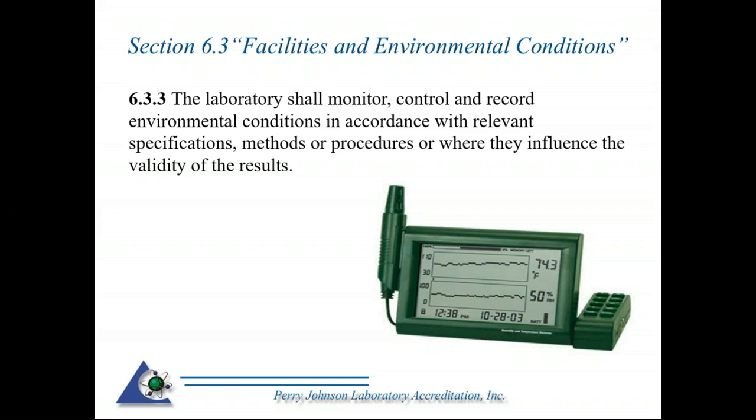Control. If your procedure or protocol is specifying environmental controls such as temperature, perhaps humidity type controls, your facility should be able to meet those criteria and control it, and perhaps set those set points and record. Typically that's captured at the time of test or calibration. Significant environmental conditions that can affect the results are typically recorded and captured at that moment when the testing or calibration is being performed.